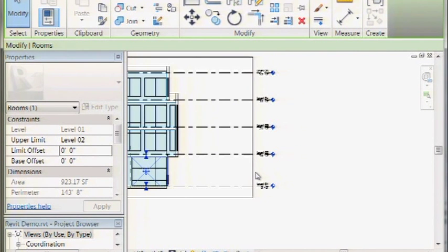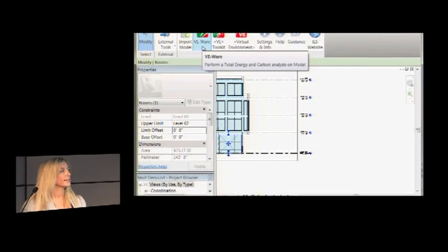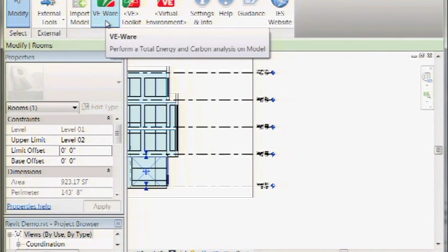Another question that we had actually yesterday was Revit MEP versus Revit Architecture. Why are these two different? Not sure, probably many of you know this already, but I'll just go over it quickly. In Architecture, our plugin will export rooms. When you're in Revit MEP, we export spaces. In Revit MEP, you will see all the rooms, but they're not going to come out no matter what you do. It just will always take spaces.